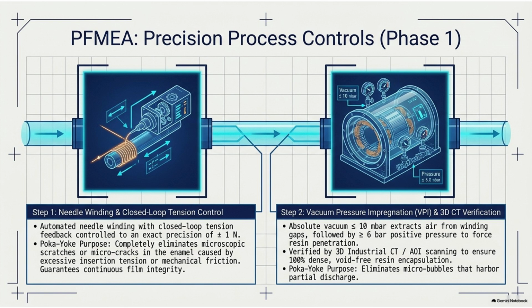The mathematical design dictates that the wire's partial discharge inception voltage. Which is what? It's the absolute minimum voltage required to even begin creating a spark. Okay. That threshold must be greater than or equal to 1.5 times the absolute highest voltage spike the inverter could possibly generate, even when the entire system is baking at 150 degrees Celsius. So they are over-engineering the wire's armor by at least 50% over the worst-case scenario? Yes. But they don't rely entirely on the wire, do they?